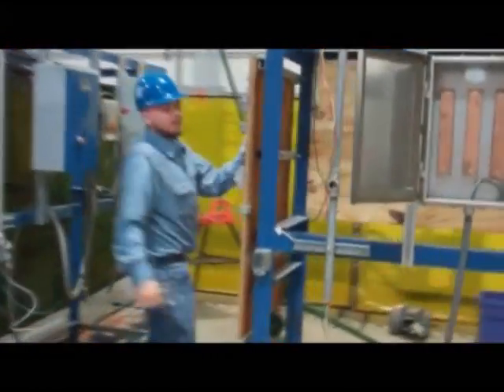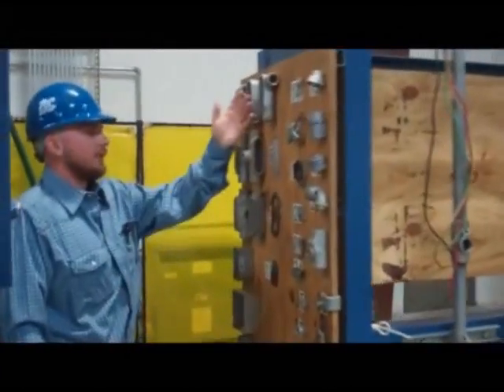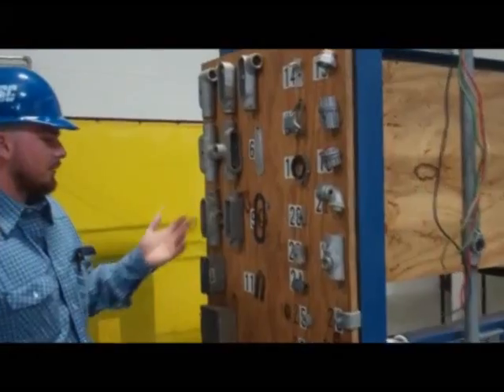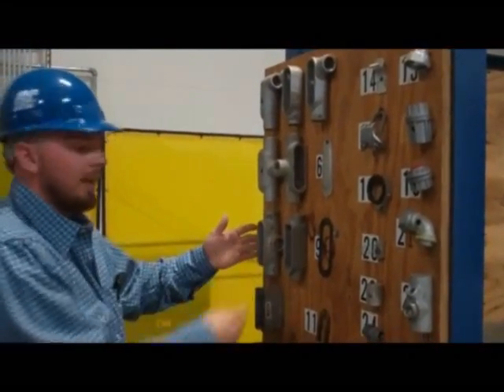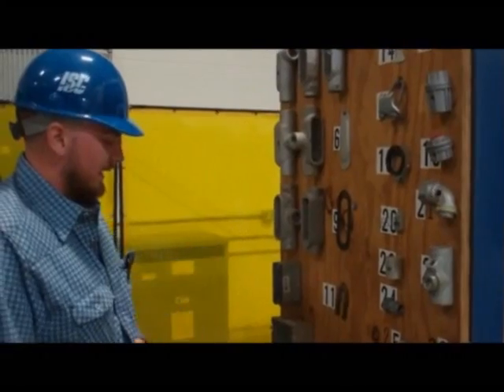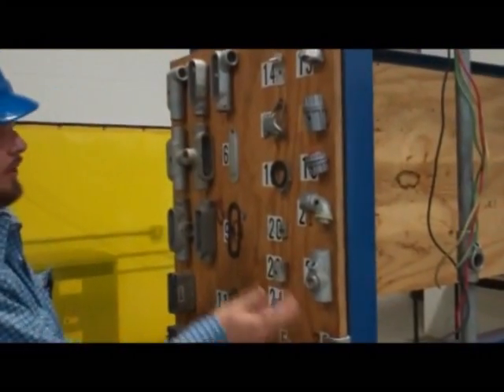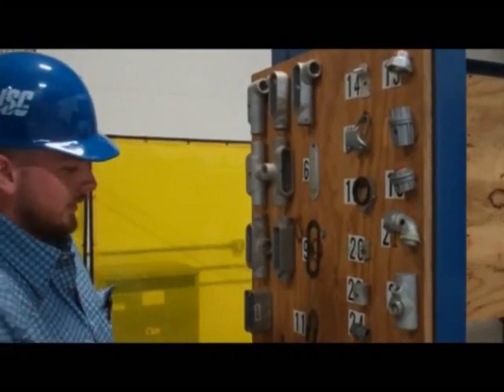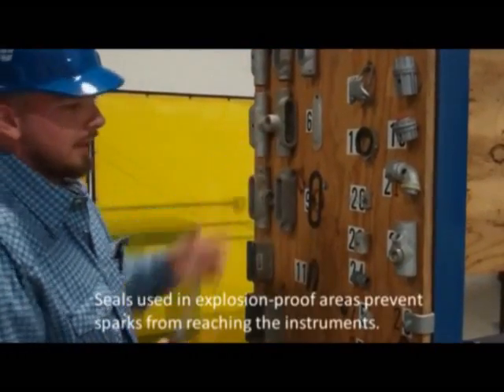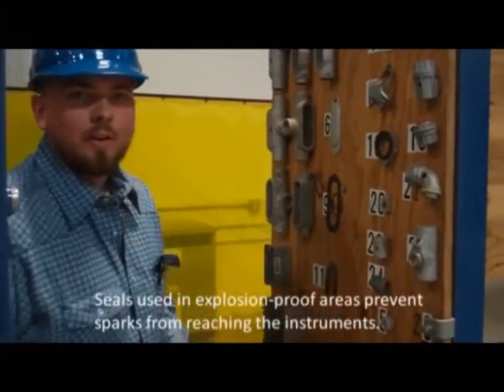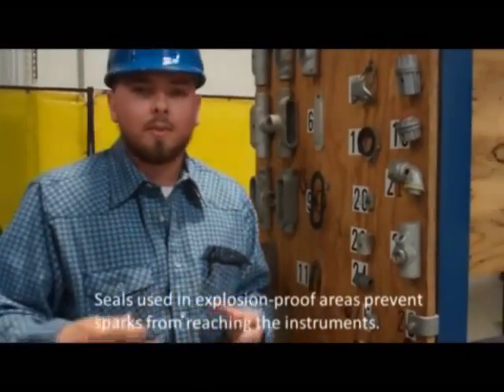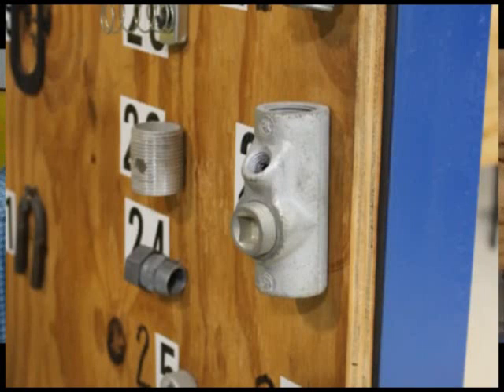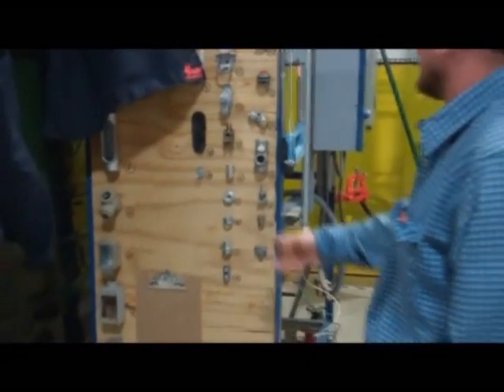Over here on this piece of plywood over here, there's some things that you would see every day being in the electrical field. These are your fittings for your conduit. You put these there so far so you can pull the wire in, or if you have to stop to hit an instrument or whatever you need to, makes it easy. These are all different kind of hardware that we use every day doing this. You got REs to little nipples to put your fittings together. These are seals in the explosion-proof areas. You need to put these, prevent a spark from the instruments inside. Here's more material, more fittings, more hardware that we use all day.